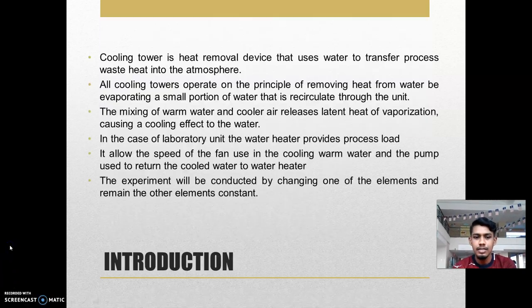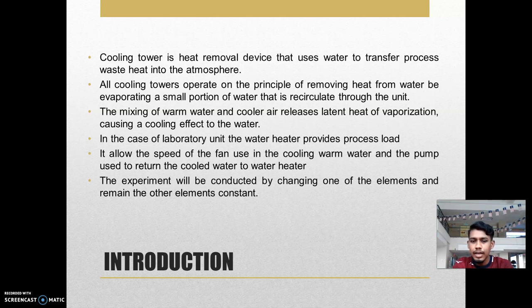My part is the introduction. A cooling tower is a heat removal device that uses water to transfer process heat into the atmosphere. The cooling tower operates on the principle of removing heat from water by evaporating a small portion of water that is recirculated through the unit. The mixing of warm water and cooler air releases latent heat of vaporization, causing a cooling effect. In this laboratory unit, the water heater provides the load, allowing the fan speed to cool the warm water, and the pump returns the cooled water to the water heater.